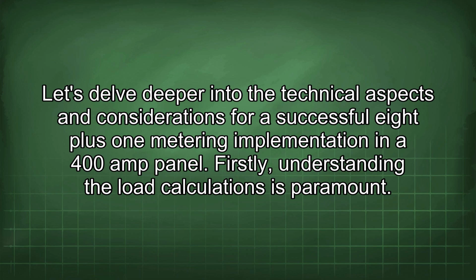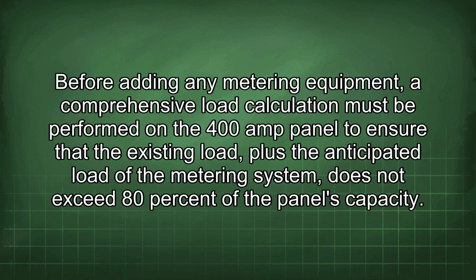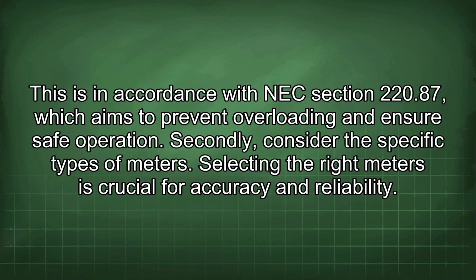Firstly, understanding the load calculations is paramount. Before adding any metering equipment, a comprehensive load calculation must be performed on the 400 amp panel to ensure that the existing load, plus the anticipated load of the metering system, does not exceed 80% of the panel's capacity. This is in accordance with NEC Section 220.87, which aims to prevent overloading and ensure safe operation.